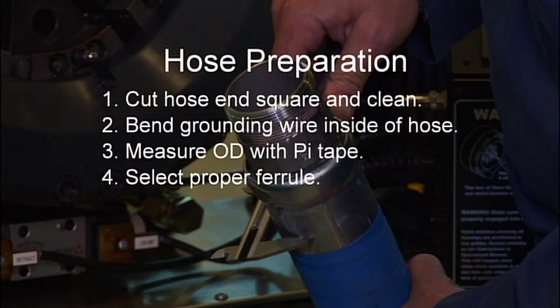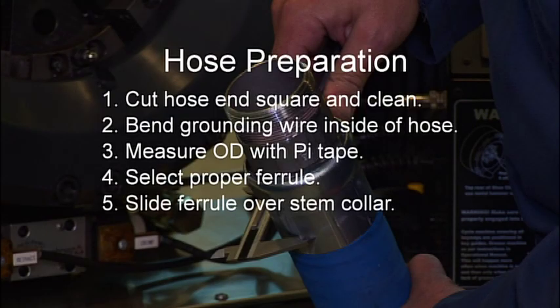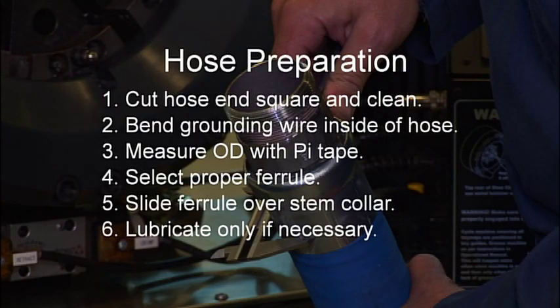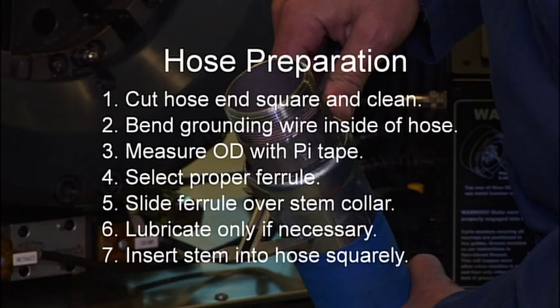Mark a line on the hose cover at the distance from the end of the hose that equals the insertion depth. This becomes a visual check to determine if the hose is fully bottomed into the fitting. 5. Slide the ferrule over the stem collar. If the ferrule has flats, be sure they line up with the flats on the hose collar. 6. Lubrication should be used only if necessary. 7. Insert the stem into the hose squarely without causing damage to the tube.